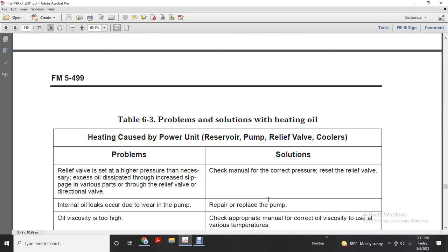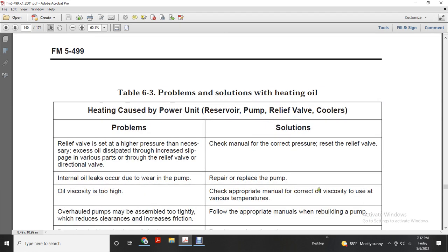Heating caused by the power unit, reservoir, pump, relief valve, or coolers. The relief valve is set at a higher pressure than necessary, so excessive oil is dissipated. Increased slipping occurs in various parts of the relief valve or direction valve. Check the manual for correct pressure. Reset the relief valve. Internal oil leaks due to wear in the pump. Repair or replace the pump. Oil viscosity is too high. Check the appropriate manual for correct viscosity for the various temperatures.